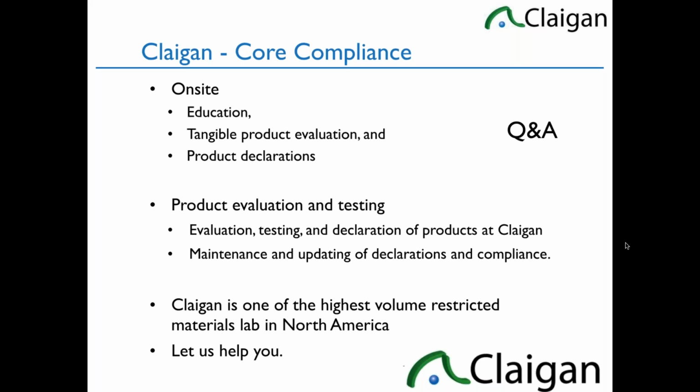And there are some really practical ways, especially when you're focusing on REACH or Prop 65. The on-site one is a far more practical way to look at it. Actually, one of the problems the IVD and big medical device companies are having is the sheer number of parts. It's not that it's hard to be compliant, it's just that human error becomes such a big factor. Large medical devices and IVD are the ones most likely to have to do incoming inspection or testing, or first article, where one batch was compliant, the next batch wasn't. It doesn't happen very often, sub 1% of the parts, but if you have thousands of parts, the math is so large that you'll have non-compliance issues all the time. So it's a little bit different for them.